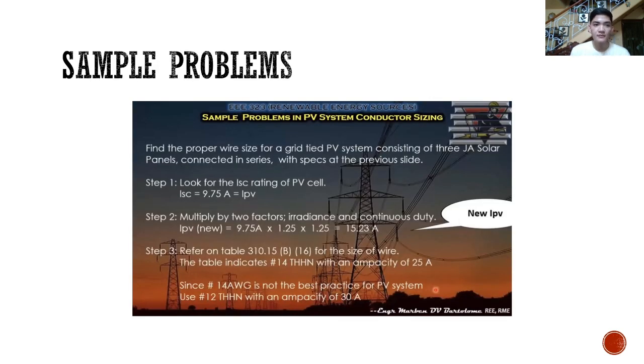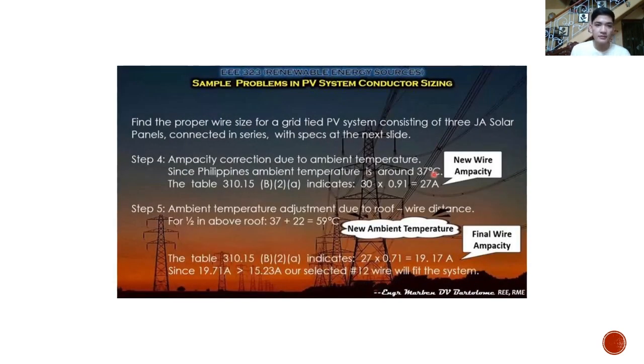Next is sample problem. For the ISC rating of PV cells is... Step 1, look for the ISC rating of PV cell. Step 2, multiply by the two factors, irradiance and continuous duty. Step 3, for the size of wire, table indicates number 14 THHN with ampacity of 25 ampere. Next is find the proper wire size for a grid-tied photovoltaic system consisting of 3 JA solar panels connected in series with specs in the next slide.